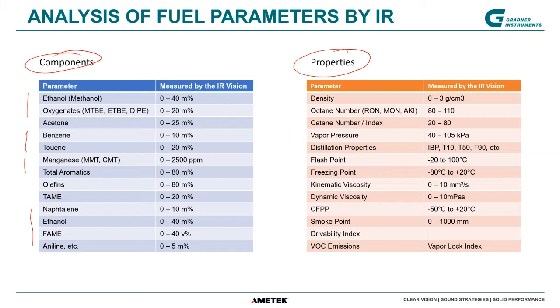Properties are not concentrations and not directly measured by infrared, but indirectly through correlation databases. With the exception of density, we have a built-in density meter. But octane number, cetane number, vapor pressure, distillation point, flashpoint, and even freezing point — those are all correlated properties which you can train into the instrument.